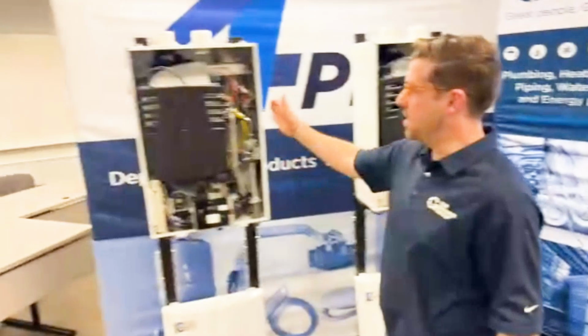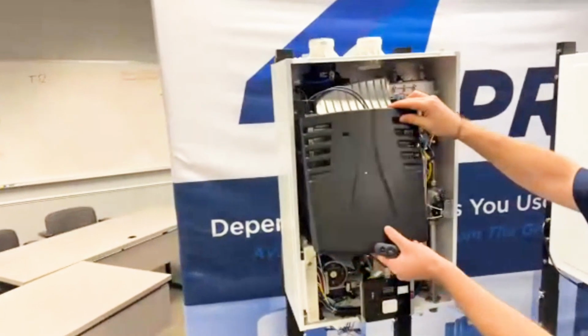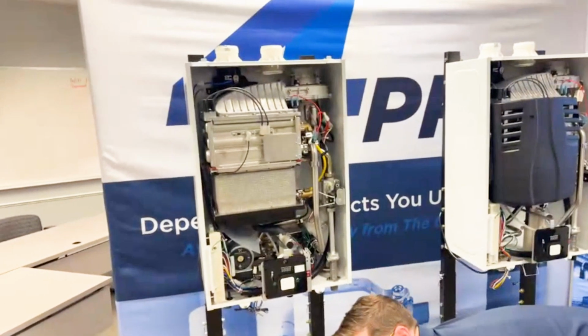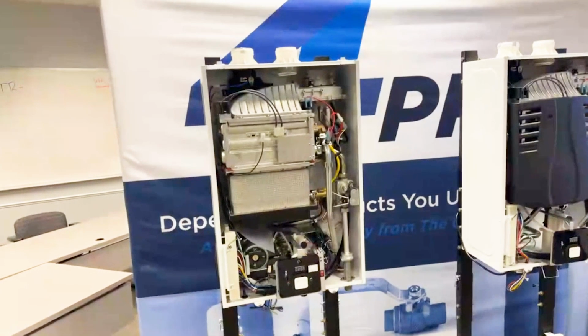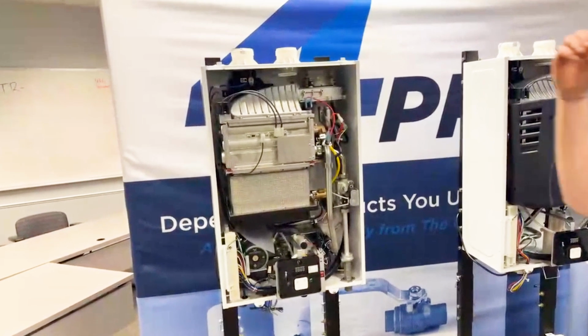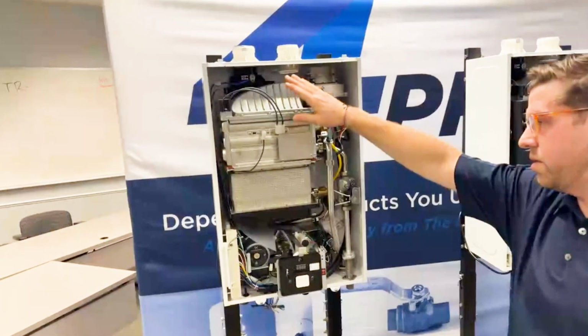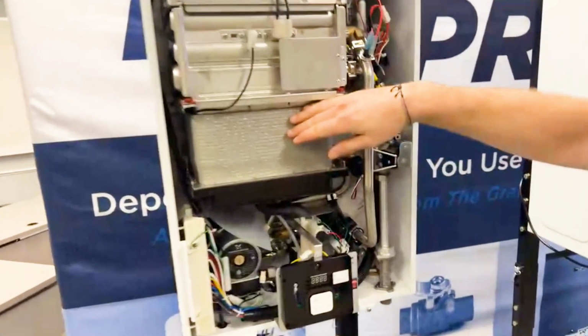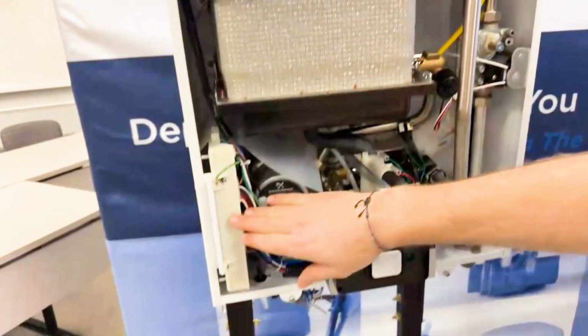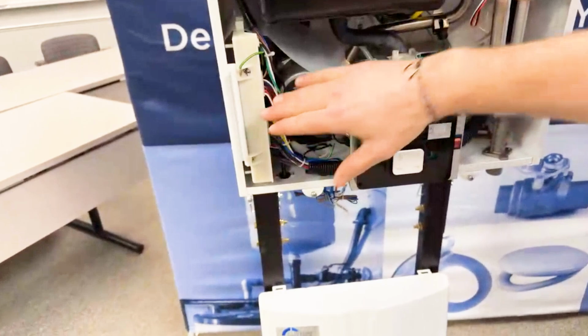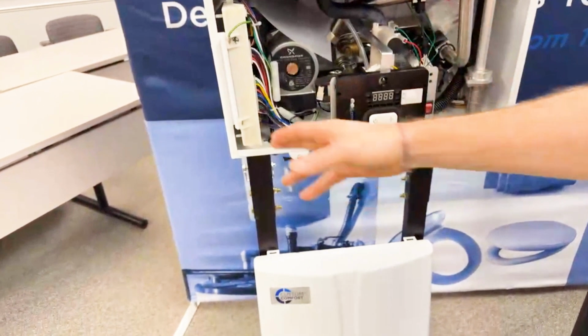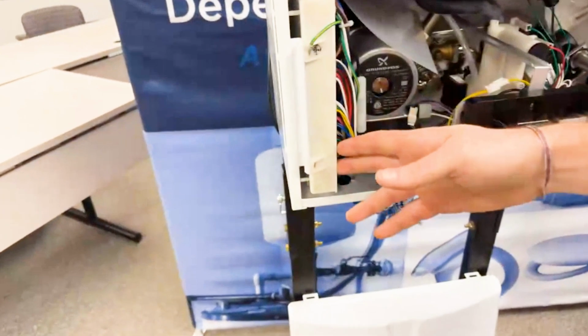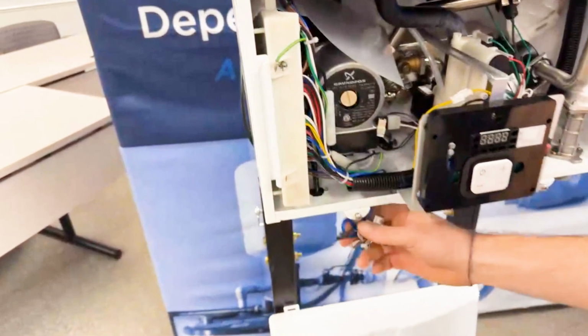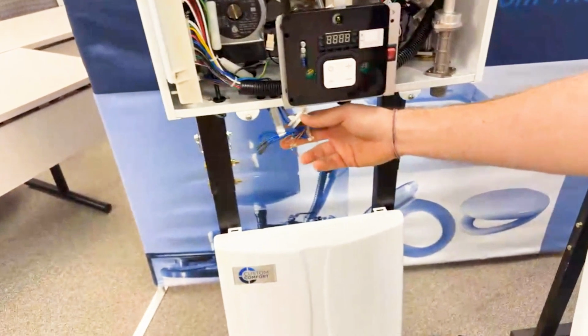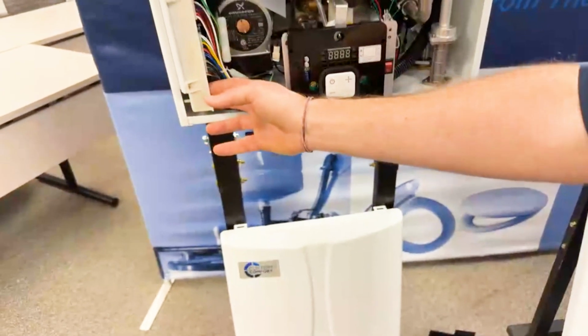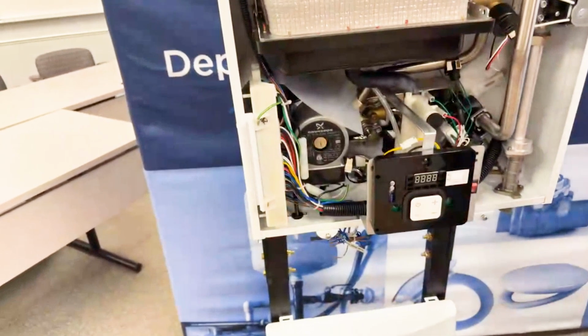So looking at the combi, pop this up. So here's our stainless steel heat exchanger, primary, secondary heat exchangers on it. We've got our control board here. That's going to be facing you in the bottom left. That's important. That's where you're going to find the dip switches. You don't necessarily need to worry about wiring to the boiler. We do give you pigtails off the bottom here, so you're not making those connections. You're just adjusting a couple dip switches on setup.